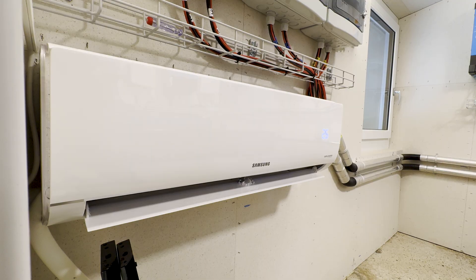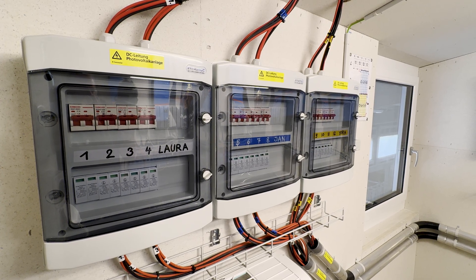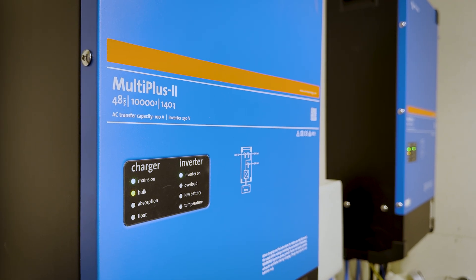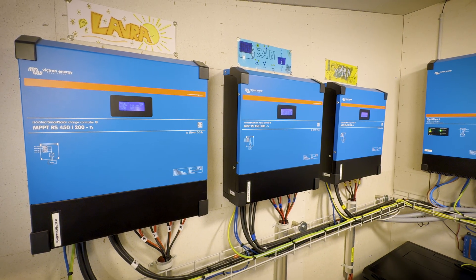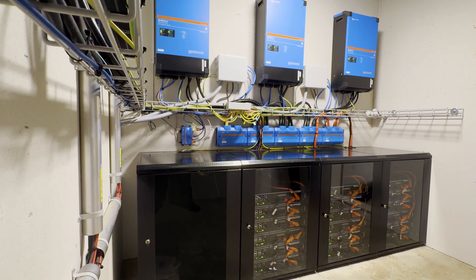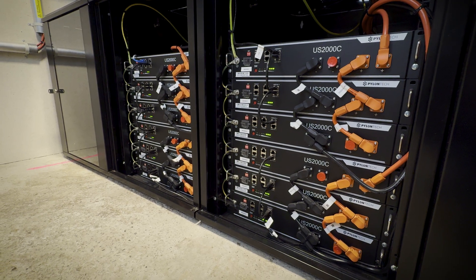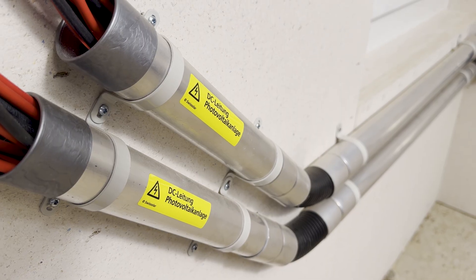The newly installed equipment is housed in a specifically built, air-conditioned room in the main barn. Inside, Danny has installed three Victron Energy MultiPlus-II inverter chargers, a Victron Energy Cerbo GX, three Victron Energy MPPT RS 450/200 SmartSolar charge controllers, and several LYNX 1000 distributors. A Samsung air conditioning unit controls temperature, and 18 PylonTech US2000C batteries are fed by around 200 solar panels on the roof.